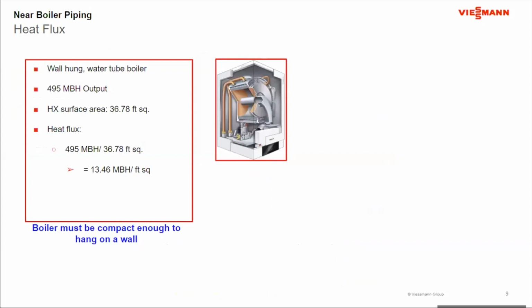Now, the next thing we want to look at is the heat flux. How many BTUs of energy am I putting through every square foot of heat exchanger? So with the wall-hung water tube boiler, again, I have 495,000 BTU output. My heat exchanger surface is 36.78 square feet. If I calculate the heat flux, I come up with 13.46, or 13,460 BTUs per square foot. Again, as a reminder, this boiler is designed to be compact. The heat exchanger and everything have to fit within the cabinet.